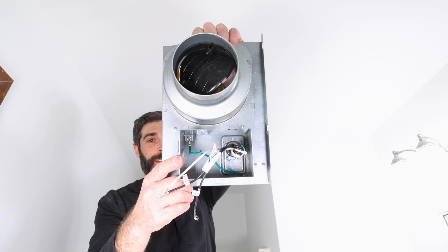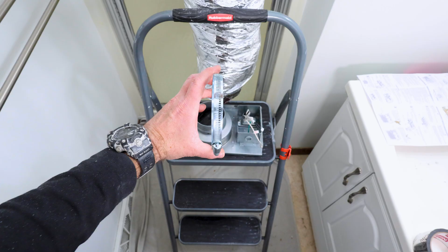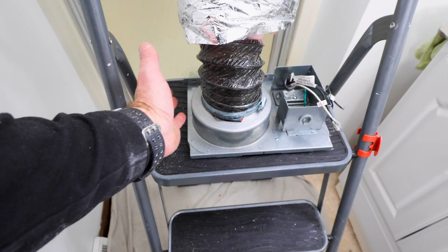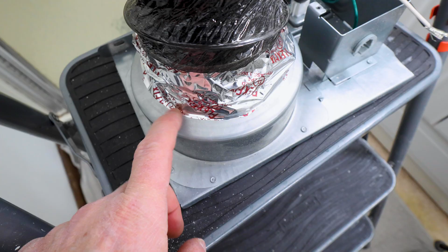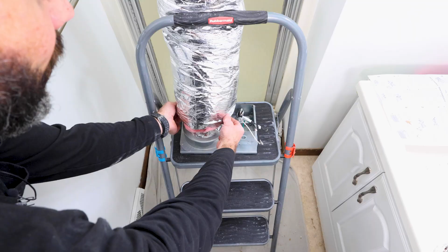Ductwork is going to be important for this installation. I use a worm drive clamp, and then I use insulated ductwork. What happens is I put the clamp over the ductwork, and then I clamp that to the fan itself. I always make sure those screws on the worm drive are facing in a direction that I can reach them later on. Then I use foil tape to seal the ductwork to the fan. That way you don't have any air leaks and everything will be insulated to cut down on condensation.